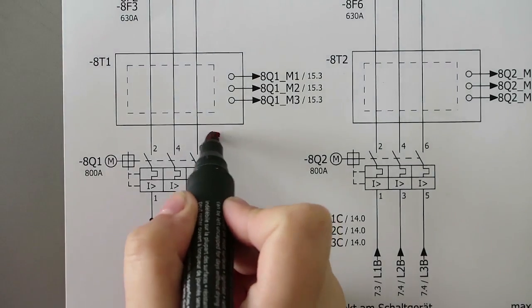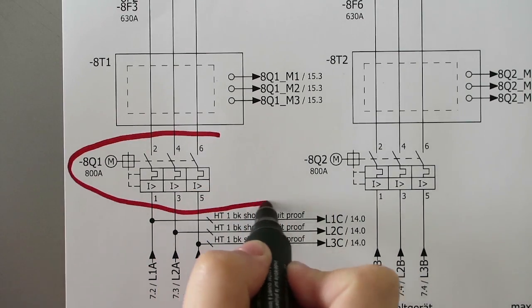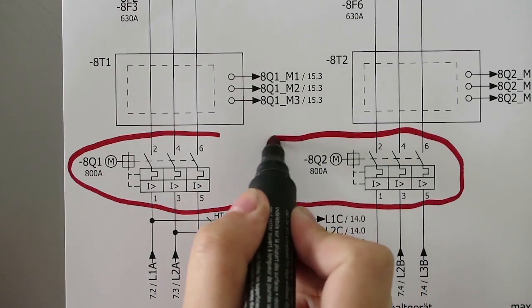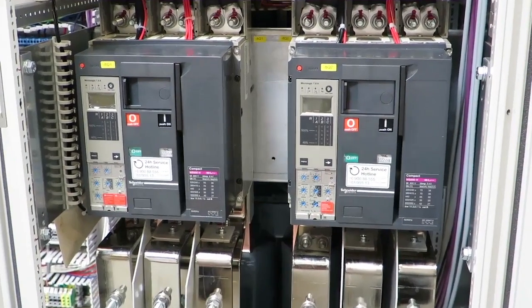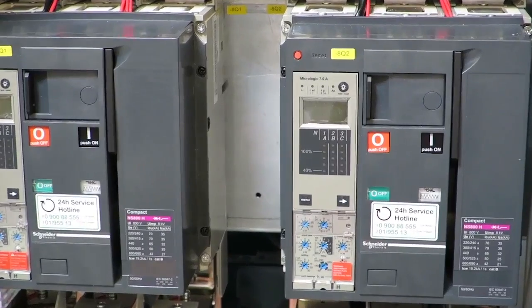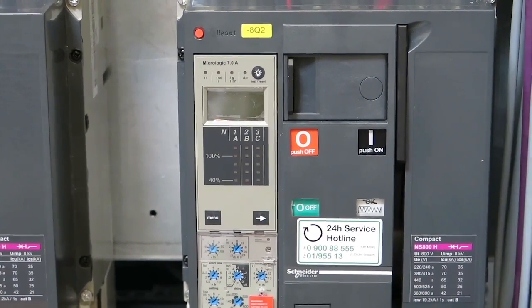To reduce the harmonic current distortion, the drive can be operated in a multipulse way. For 12-pulse, we will equip the drive with two rectifiers, two sets of fuses, and two circuit breakers.